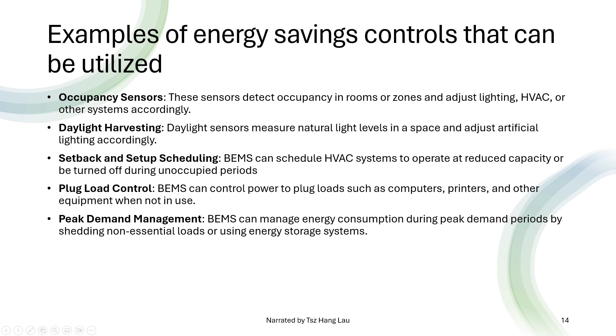Setback and setup scheduling. BMS can schedule HVAC systems to operate at reduced capacity or be turned off during unoccupied periods, such as nights and weekends. By adjusting set points during this time, energy savings can be achieved without compromising comfort. Plug load control. BMS can control power to plug loads such as computers, printers, and other equipment when not in use. By automatically turning off or putting devices into low power modes during idle periods, energy savings can be realized. Peak demand management. BMS can manage energy consumption during peak demand periods by shedding non-essential loads or using energy storage systems. By reducing demand charges or avoiding peak pricing, significant cost savings can be achieved.